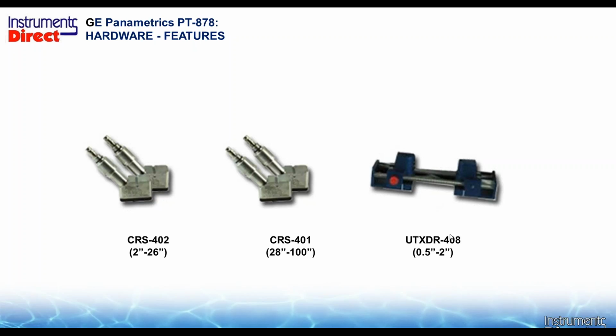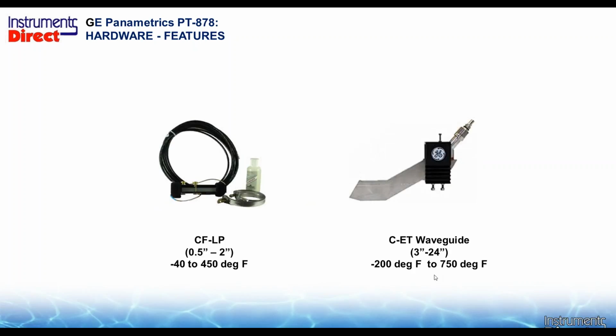The small pipe sensor has a smaller footprint, and it's all one little package. This is a 4 megahertz system that works from 0.5 to 4 inches. And of course, we have some more in the family. It's a high temperature version, which is pretty much the standard now when you buy a kit. You get the high temperature one as opposed to the low temperature small pipe sensor.